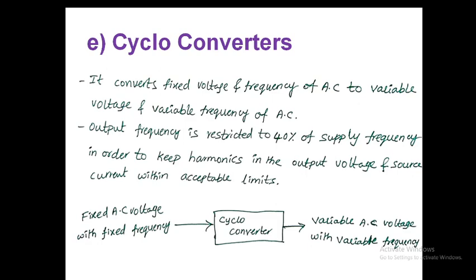The next type is cycloconverters, used to convert fixed AC voltage and frequency into variable AC voltage and variable frequency. The output frequency is restricted to 40% of the supply frequency in order to keep harmonics in the output voltage and source current within acceptable limits.